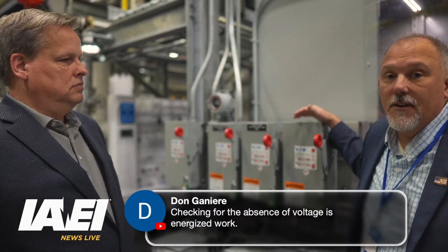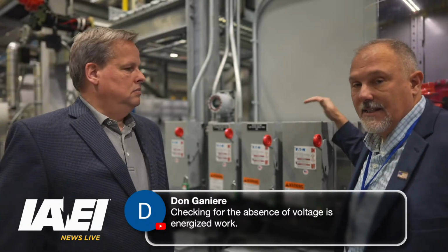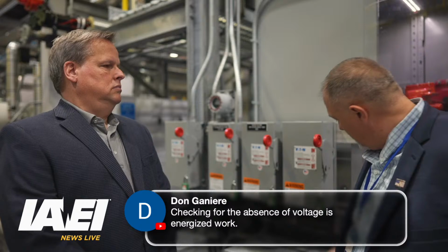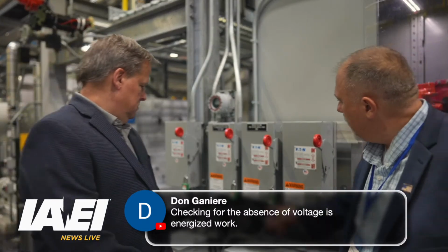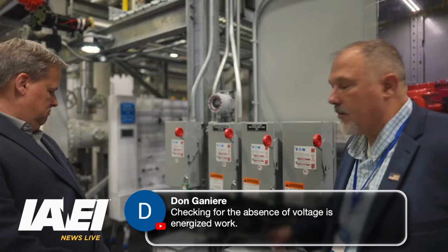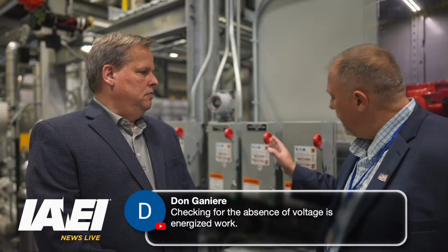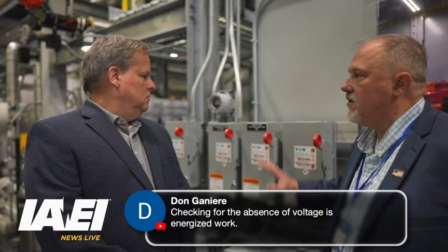And you know what I always said? There is nothing you do that is not energized work. Even when you establish an electrically safe work condition, you're still doing energized work in that process, in my opinion. Now, what I can do, and this is where a disconnect switch like this is very helpful, is establish an electrically safe work condition. If this supplied the transformer, which I don't think it does. Oh yeah, it does. That's the 480 volt primary for this transformer. Because this is right next to the transformer and I can physically see it goes to this transformer, when I turn this to the off position, I've increased my confidence level that I have removed power from that transformer.